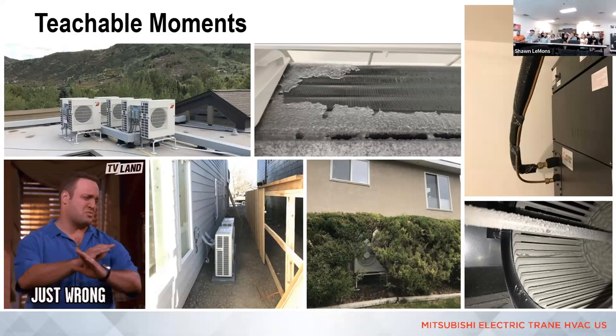Top right corner, notice the copper line set—an AC installer put this in without realizing both sides need insulation, so they picked the long line set. Bottom right corner, dust and debris during construction will soil the coil, which isn't good—you'll lose efficiency, so try to maintain your filters if there's construction going on.